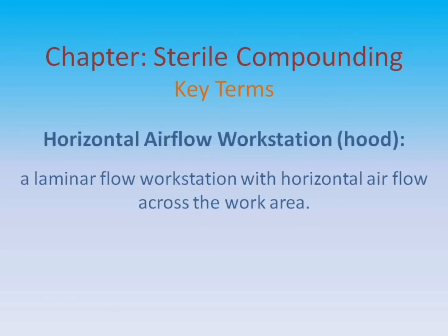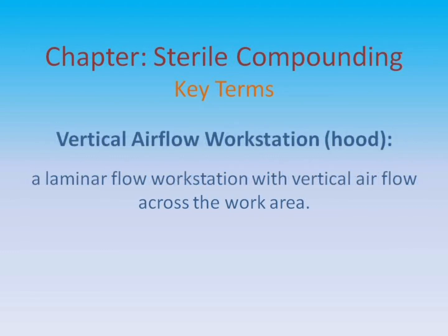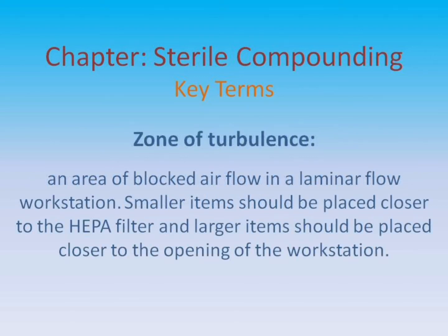Horizontal airflow workstation, or hood: a laminar flow workstation with horizontal airflow across the work area. Vertical airflow workstation, or hood: a laminar flow workstation with vertical airflow across the work area. Zone of turbulence: an area of blocked airflow in a laminar flow workstation. Smaller items should be placed closer to the HEPA filter, and larger items should be placed closer to the opening of the workstation.